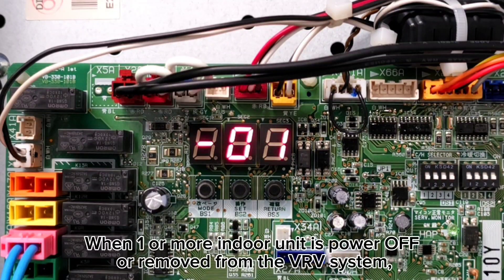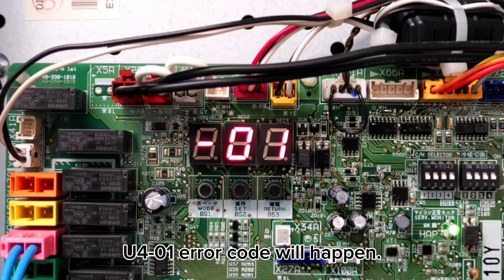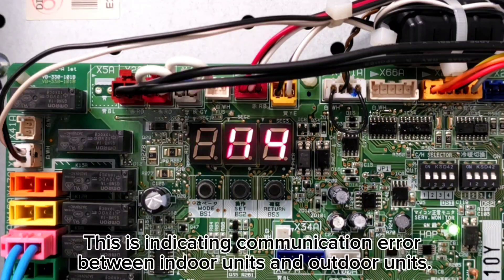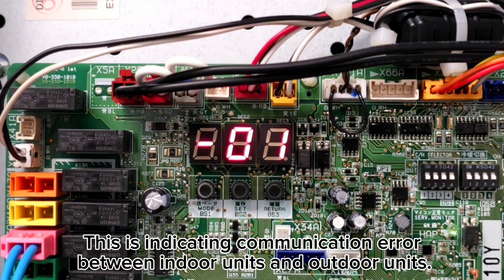When one or more indoor units is powered off or removed from the VRV system, U4-01 Error Code will happen. This indicates a communication error between indoor units and outdoor units.